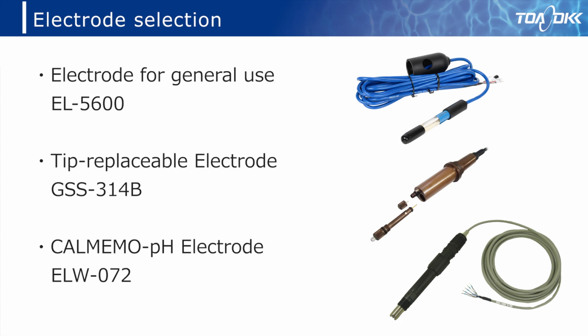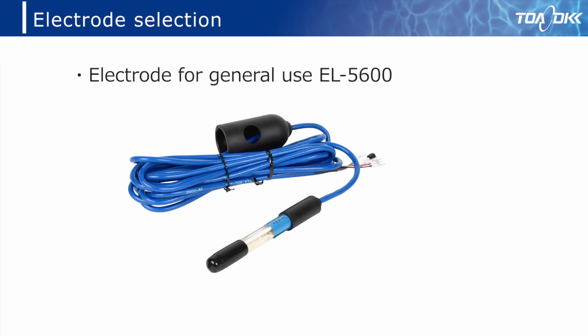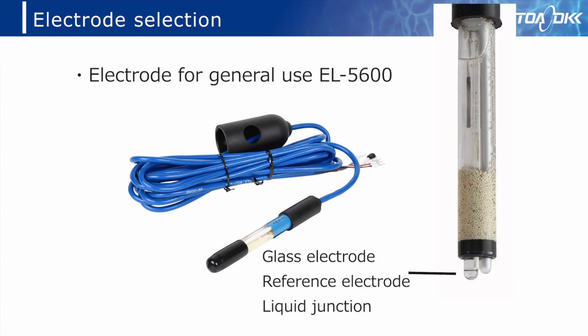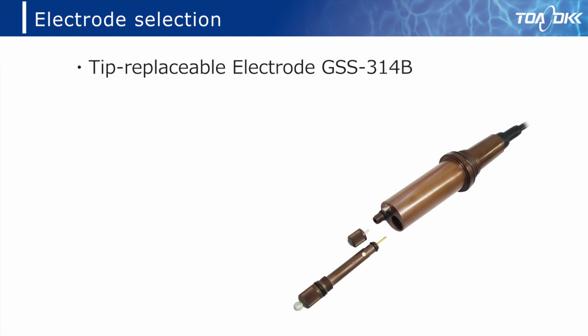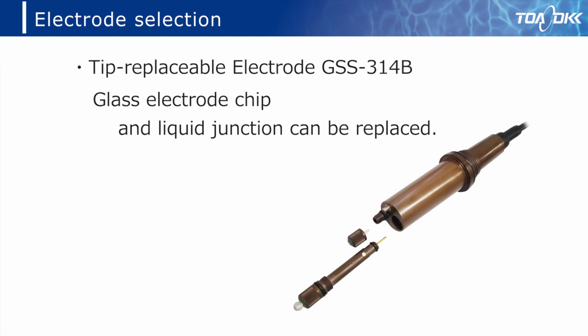This section explains selecting the specification of the electrode. There are 3 types of electrodes available. Electrode EL5600 for general use has been proven in the past. Previous MAC-355 and other devices adopted it. The glass electrode, comparison electrode, liquid junction and lead wire are integrated. As for the tip replaceable electrode GSS314B, the glass electrode chip and liquid junction are replaceable. Replacement of these tips achieves maintainability and low running costs. This can help reduce maintenance expense compared to replacement of the whole electrode.